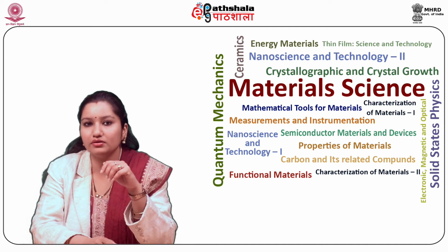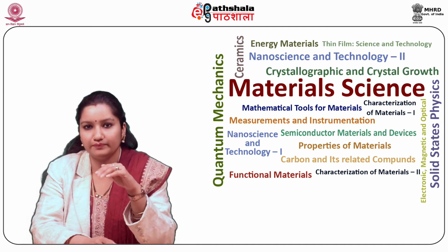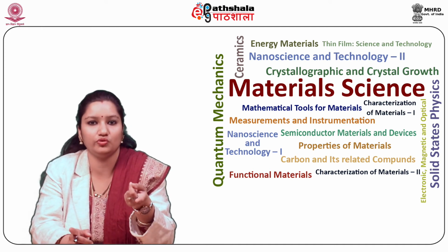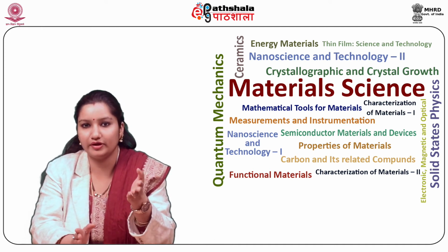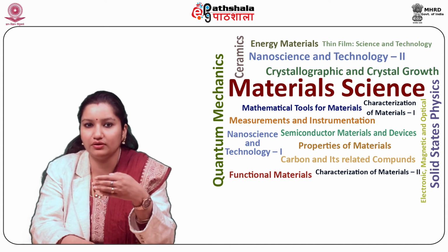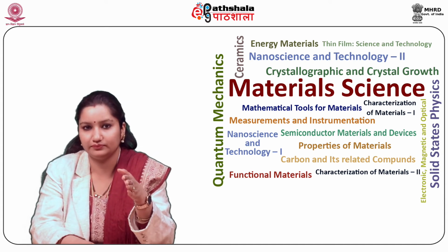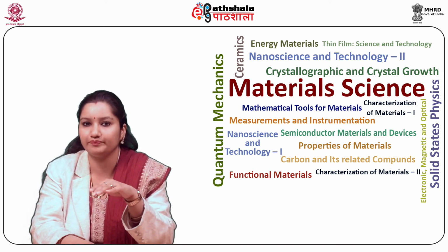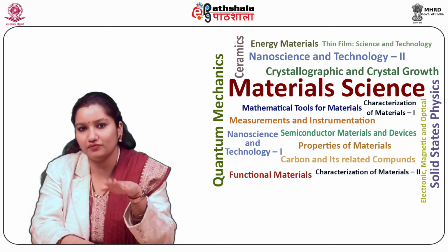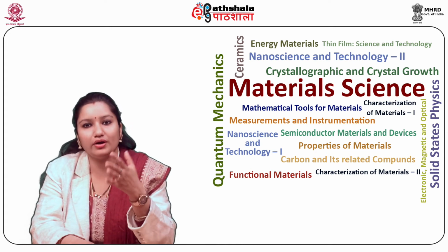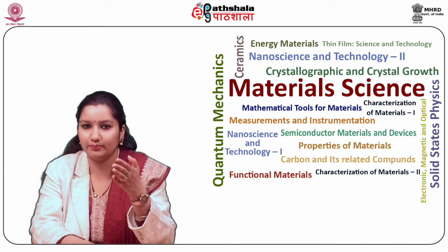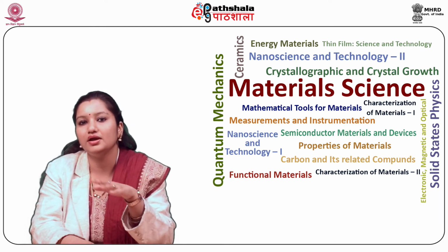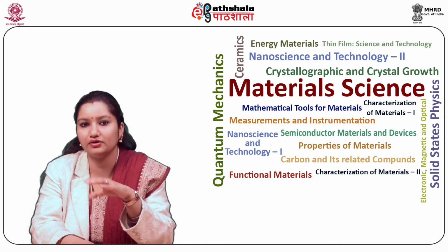Various techniques are used. The first one is the spark cutter. In this, electric discharge between the wire and the specimen is used to cut the metal by removing small particles of metal from the surface of the specimen. The second one is the focused ion beam or FIB. A thin slice of the sample is cut by an ion beam in a scanning ion microscope. The main advantage of this method is that it allows for selective thinning at desired locations by cutting trenches in the sample.